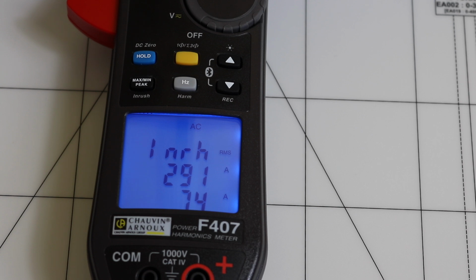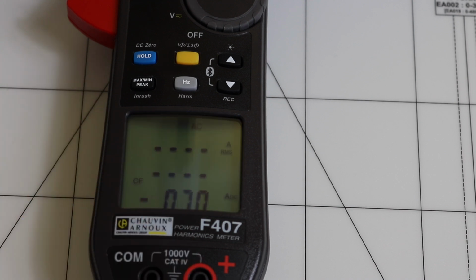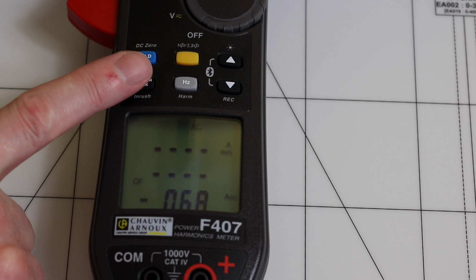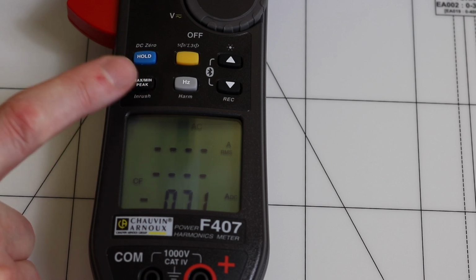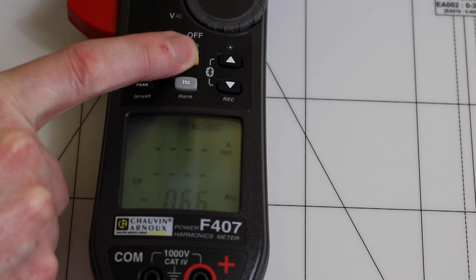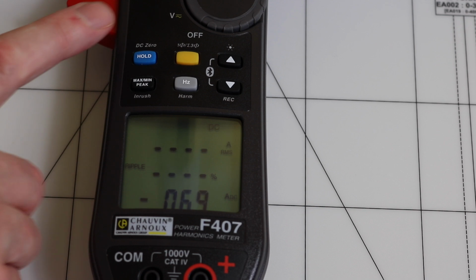Slightly unusual, I've not seen that kind of trigger level on an inrush function before, but there you go, that's what Chauvin Arnoux have decided. So we've seen it work in AC okay. What we also have is a DC inrush capability as well on this instrument, which again is quite unusual. Usually when I press the inrush button, when we switch to DC, which we do with the yellow button here, AC, DC, go to DC there.